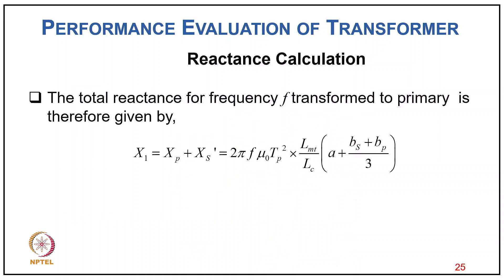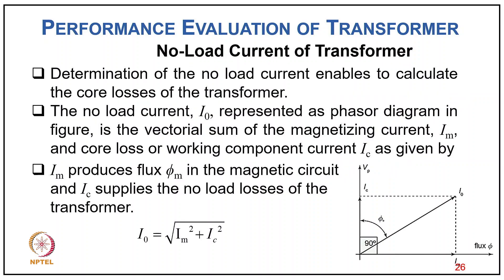The total leakage reactance referred to primary is X1 = 2πf × μ₀ × Tp² × LMT/Lc × [a + (bs + bp)/3], where LMT is the mean turn length of both windings combined.